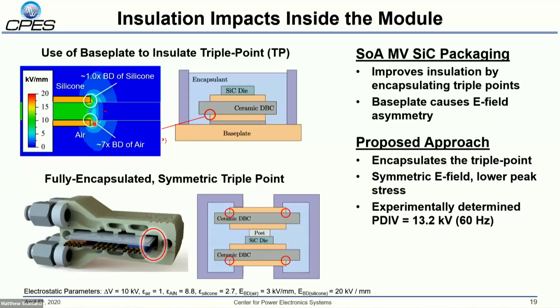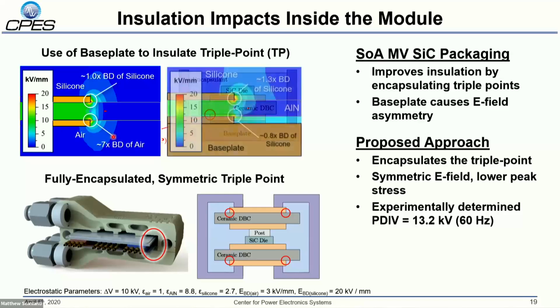So you're certainly going to get partial discharge here. Once we encapsulate both sides, we're now on the order of 1.3 times the breakdown strength of silicone, and about 0.8 times the breakdown strength of silicone. So we're getting closer to the safe region, but one of the problems the base plate causes from an insulation standpoint is it causes an asymmetry in the formation of the electric field, which you can see with these relative breakdown strengths.